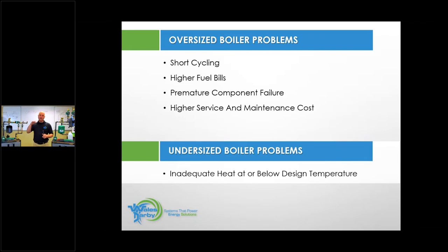We want to get these boilers to come on and run at what we call steady state. So a boiler's always the dirtiest when it starts and when it shuts down. So we want to try to get a boiler to come on, run steady state for as long as it has to, satisfy the demand, shut off, and wait. Every component on that boiler has been cycle tested, and it's going to have so much life in it. So that's why we don't want a boiler short cycling, because we'll wear out the components faster, which again, should mean higher service and maintenance costs.